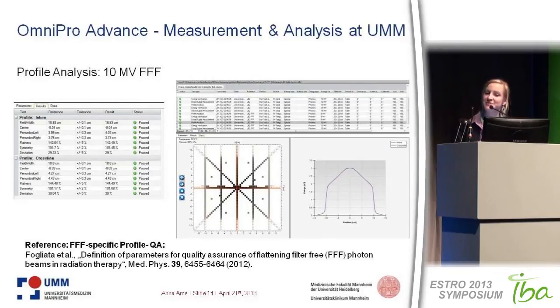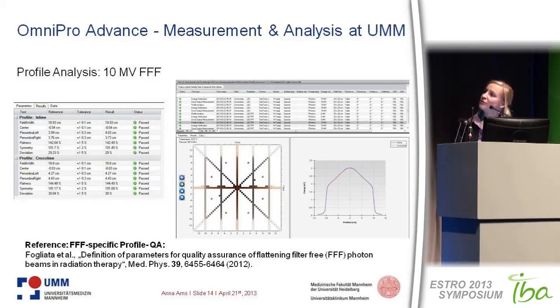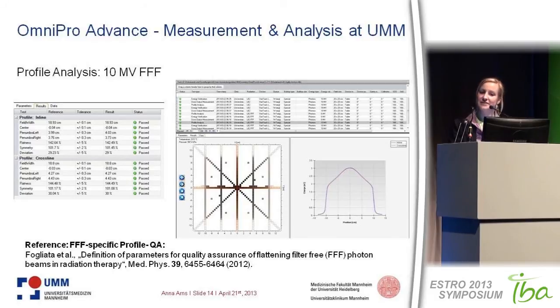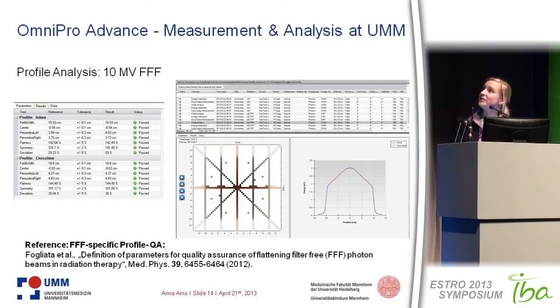This might be interesting for most of you — the new flattening filter free technique. This is how the FFF profile looks; we generated this data directly after our acceptance testing. We have to set the tolerance for flatness quite high because flatness is simply not given anymore. If you compare to your reference data and everything is fine, everything is green. We are currently developing a QA procedure for flattening filter free, referencing the paper by Fogliata et al., which analyzes the slope of the profile.